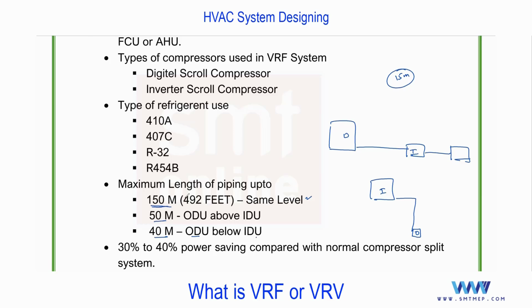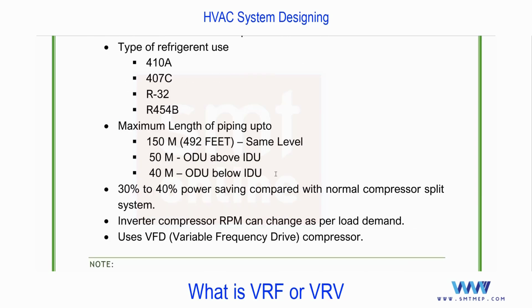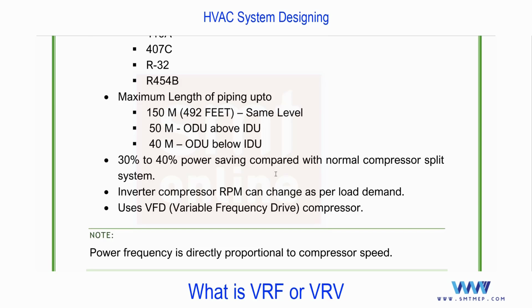Again, you need to refer to the manufacturer's catalog at the time of pipe sizing, and we have a separate topic on pipe sizing for VRF using the vendor's catalog, or we have software also, because this is a precision type of machine compared with the other types. So remember this guideline, it may be asked in interviews. Next point, you see 30 to 40% power saving or energy saving compared with a normal compressor split system. Again, as I said, in a split system also you'll find this inverter type scroll compressor. In that case, you'll find very close power saving.